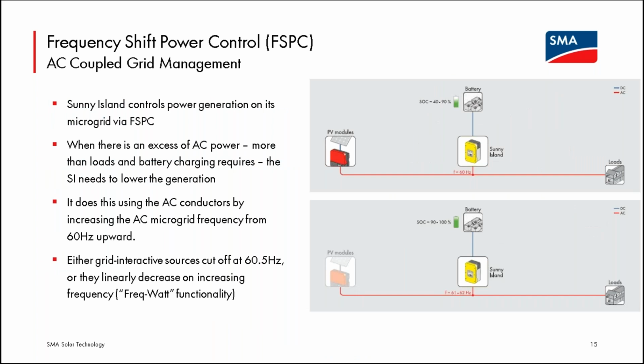The Sunny Island operates an AC microgrid if it is isolated from a utility grid, and it is creating that 120 volt, 60 hertz AC utility power that is powering the microgrid. If there are PV inverters on that grid, it's possible that there may be excess power. The PV inverters are producing more than the Sunny Island needs to power its loads or charge its batteries. The way it controls power sources on its microgrid is by frequency shift power control, FSPC. If it sees more power than it needs, it will raise the AC frequency from 60 hertz. And SMA Sunny Boys are smart enough to respond to that linearly.